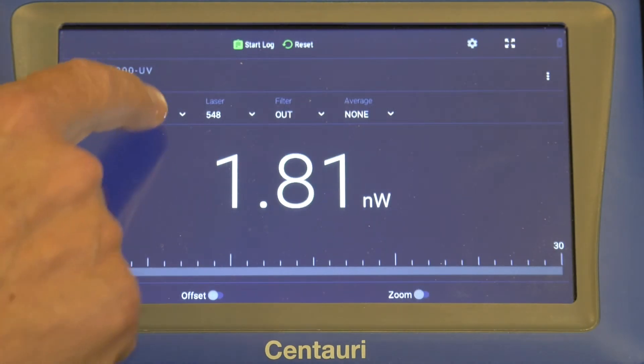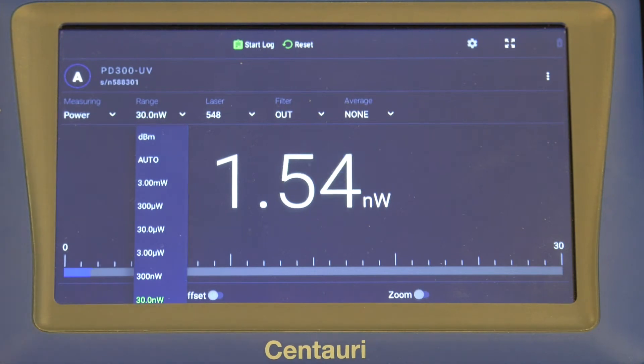So the usual approach is to divide the overall power range of the instrument into several scales or ranges — we use those two terms interchangeably — and thereby achieve a useful overall dynamic range of the power meter. For example, looking again at the Ophir PD300UV, here you can see the scales into which the measurable power range is divided.